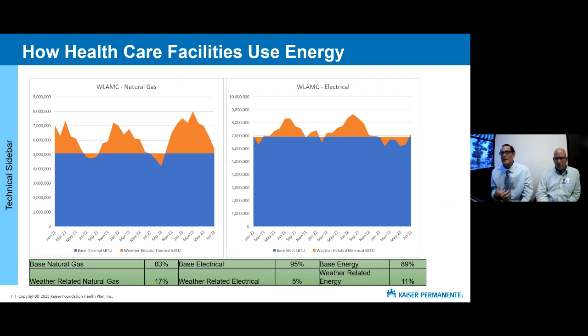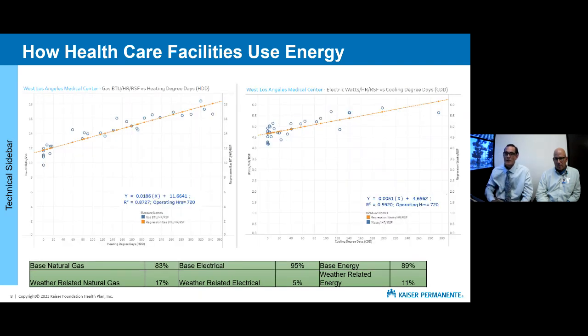Now, mathematically, the way we find that is we run a linear regression, or two linear regressions. We take the natural gas data and run a linear regression against heating degree days, HDD. Then we take the electrical data and run a linear regression against cooling degree days. What we're looking for there is the y-intercept - that tells us where that blue rectangle goes, and the part above the y-intercept tells us what the weather-dependent usage is.